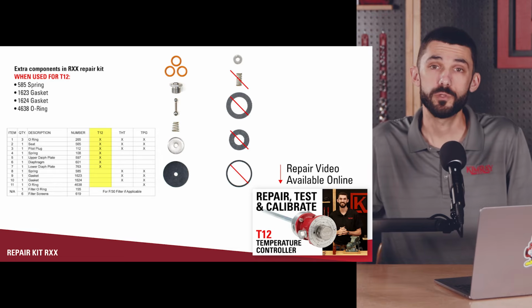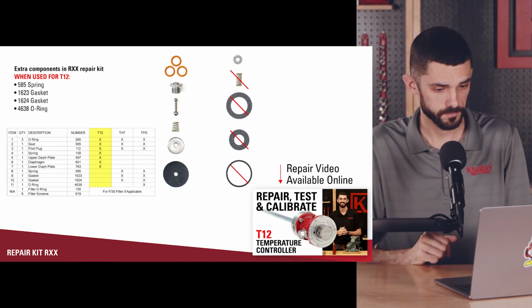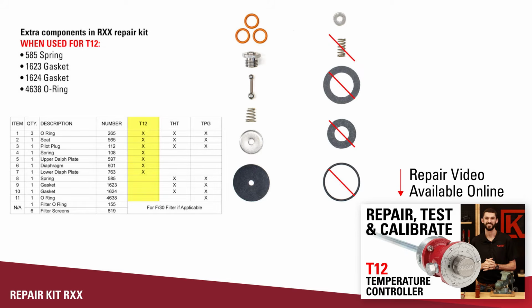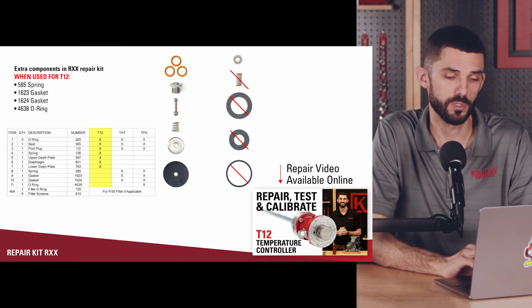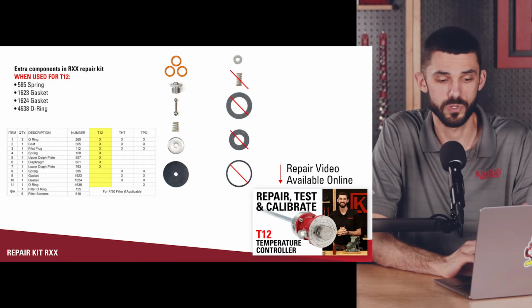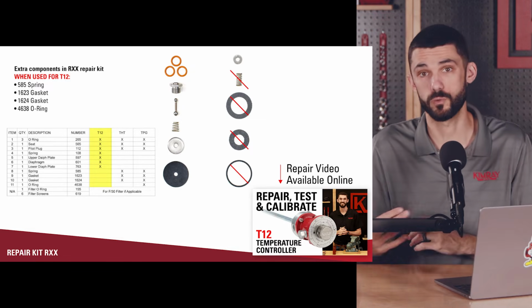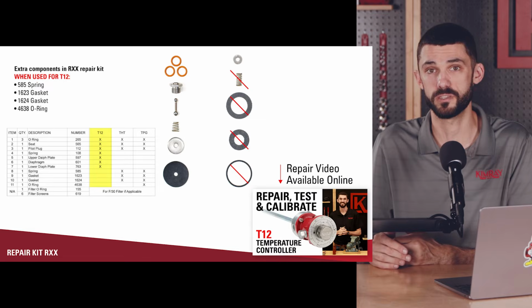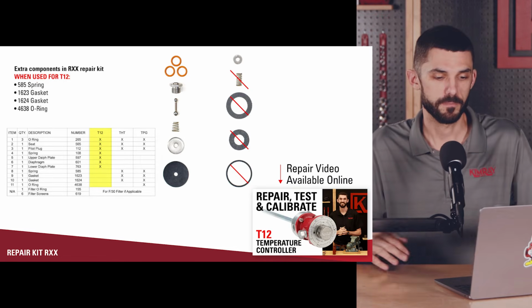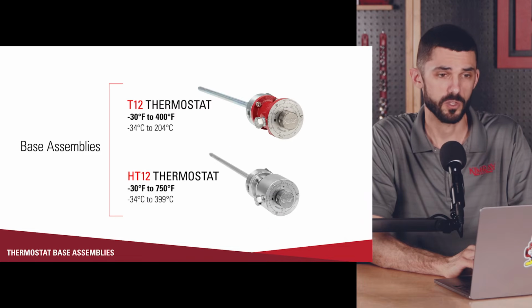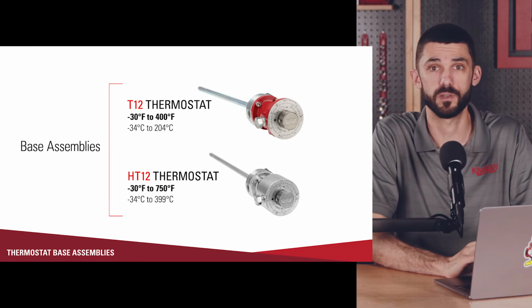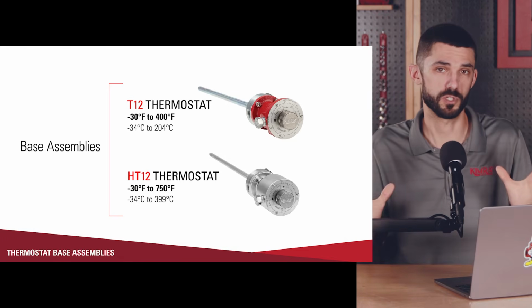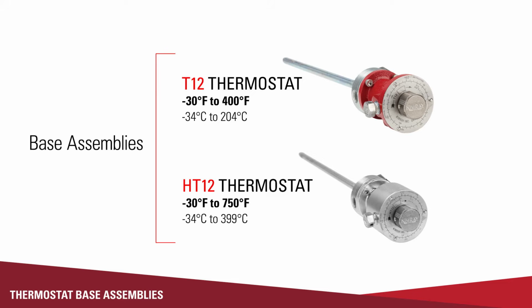I want to talk through a few key components of the T12. There's a few parts to replace. We actually have a video on temperature controller repair, and we'll link to that below this video. The areas of concern for the temperature controller is the pilot plug. So when you are supplying this either with natural gas or compressed air, you want to make sure that it's clean and dry. And you also want to make sure that you are operating within the temperature range for that specific temperature controller. So there we have two options for that. We have a T12 and then we have an HT12.